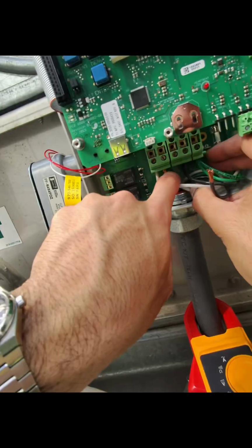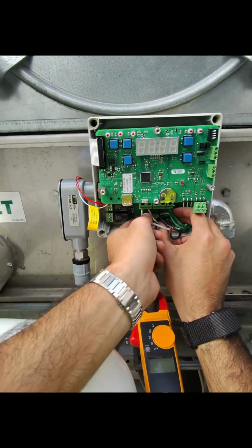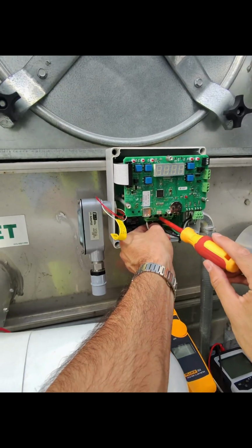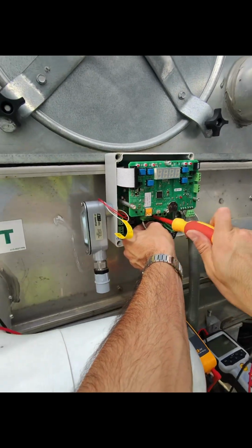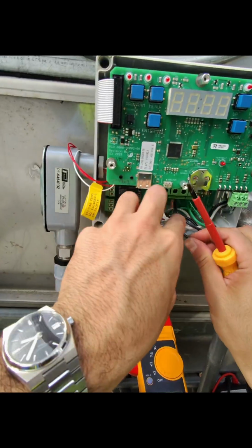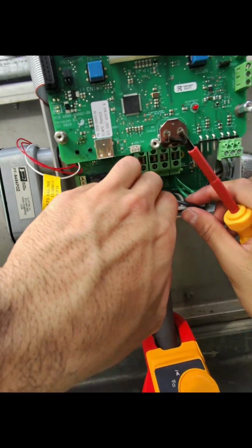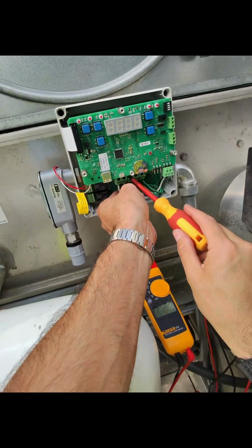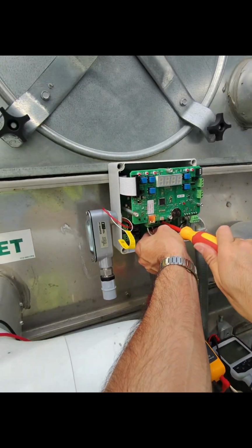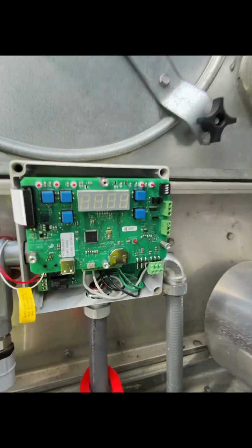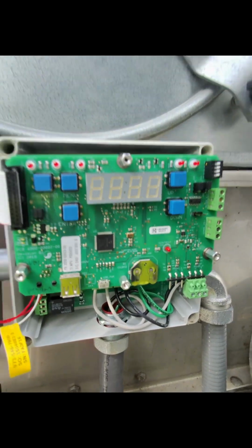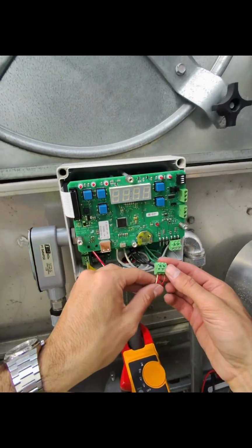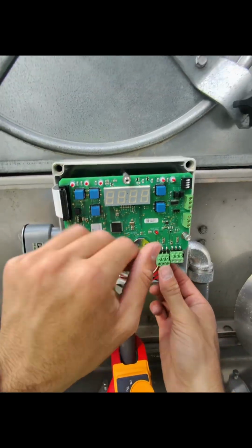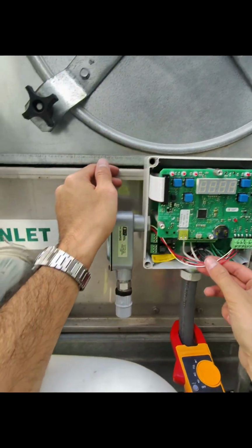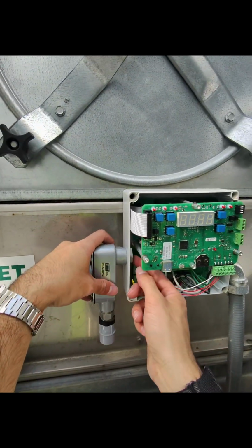to the contractor. Here, you can see the terminal blocks on the Tracer 1 where your power wires come in and out. Tracer 1s have integral GFEP protection. This means that you can feed this with a regular breaker and does not need to be rated for that GFEP protection, which is common amongst heat trace. Once everything is securely tightened, I reattach the sensor, which goes on the left of the 2 sensor inputs for probe 1.